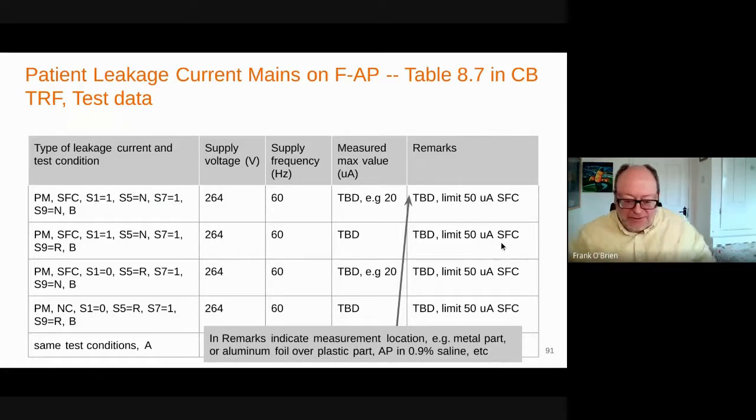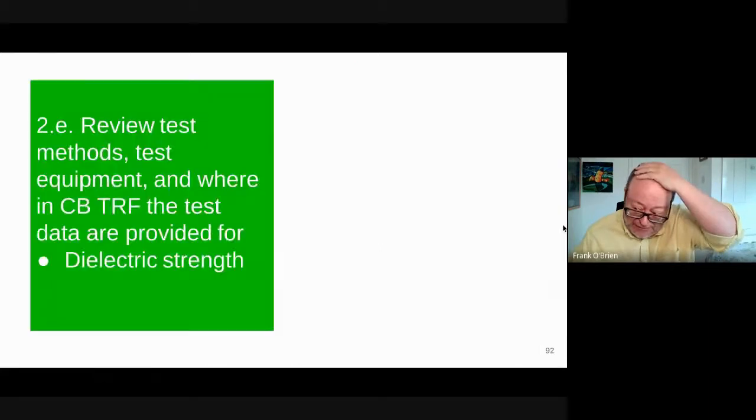However you want to do it. So the test report will have all that data. And it would be the before humidity where we've had equilibrium, thermal equilibrium, and then after humidity where we're more worried that it was in the chamber for a while, and then we took it out and did the test. And so you've got all that data both before and after for all those cases. Okay.